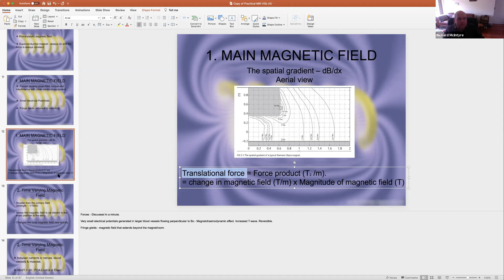So what we've covered so far is the main magnetic field, caused by the superconductive magnet. It's causing projectiles, it's causing turning force, it's causing interference with other electrical equipment, it's setting up small electrical potentials, and it has fringe fields—it doesn't just stop at the bore of the magnet, it carries on until the door. That's all because of the main magnetic field that's always on. It never changes amplitude, it's always on.